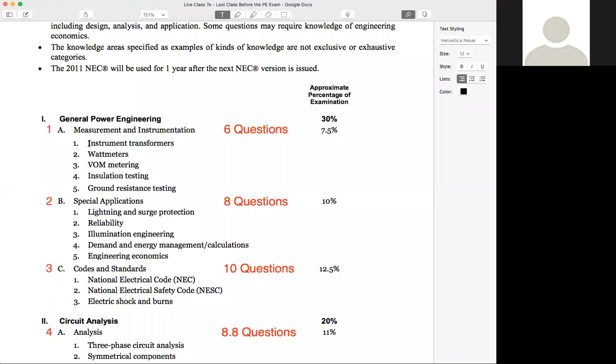So the whole point of instrument transformers almost always is we're stepping down those values to a value that our equipment can handle, right? And then our relays themselves, when they're telling us, okay, I'm seeing 220 volts here, or I'm measuring 550 amps, what they're really doing is using whatever the built-in transformer ratio is. They're using that ratio to multiply whatever the true reading is, and then they're giving you essentially the extrapolated value, or the value that's on the line. So it's pretty interesting. CTs, they call them donuts sometimes.